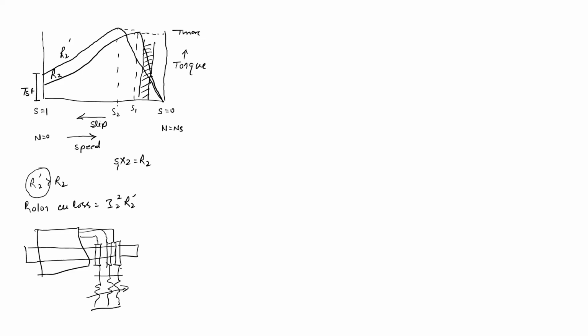So there is no external resistance in the rotor circuit, and therefore under running condition only the resistance of the rotor will be there, and it will give a better efficiency. But in the slip ring induction motor, there is continuous rubbing over the brushes. Frequent maintenance is needed to replace the brushes, and sparking over the brushes also takes place.